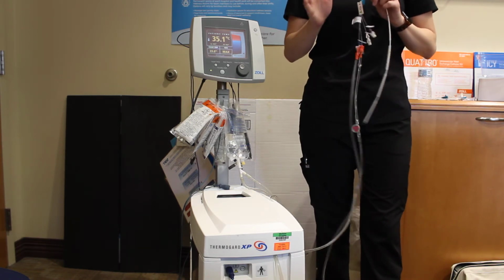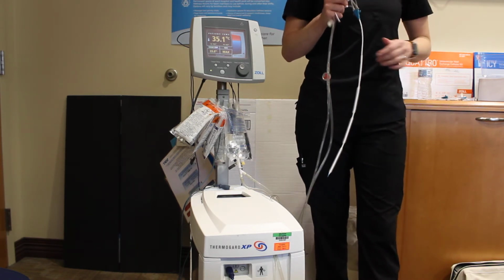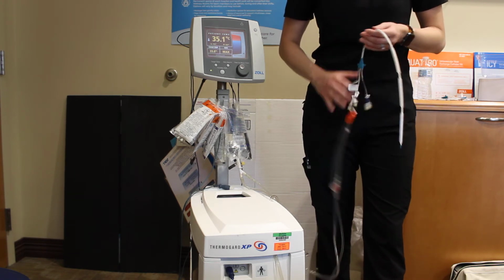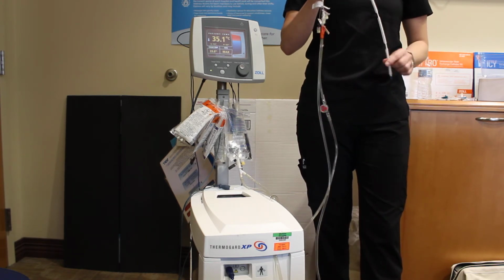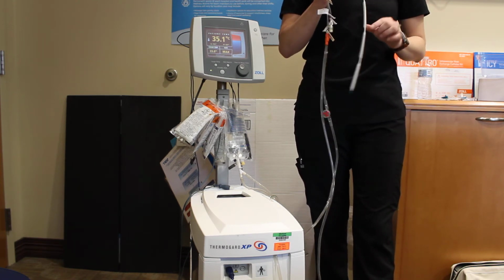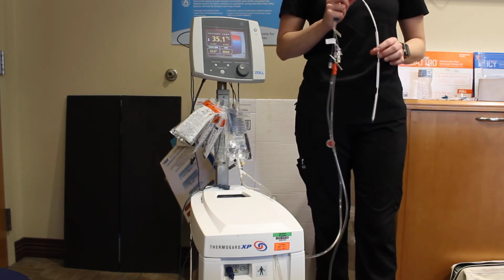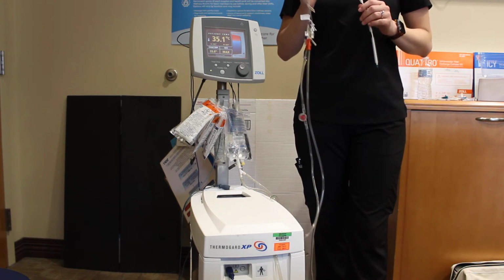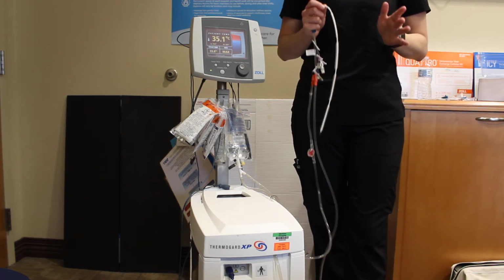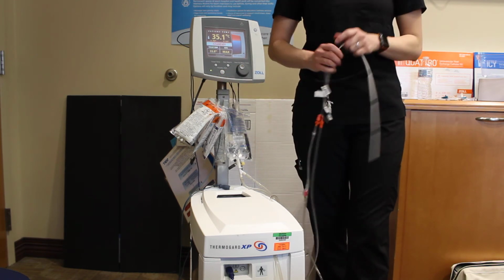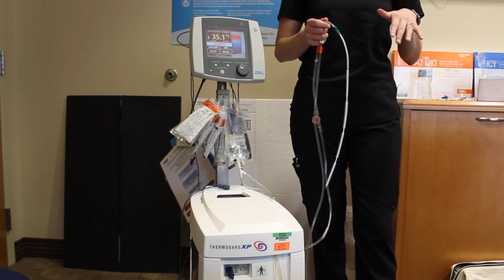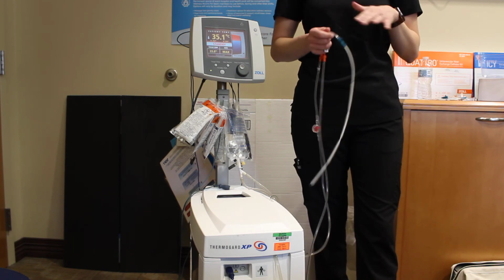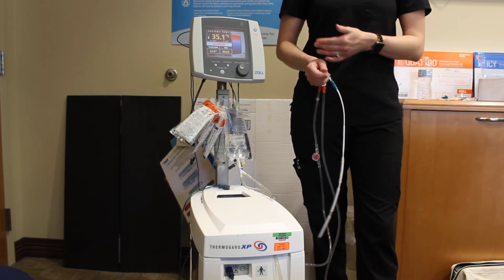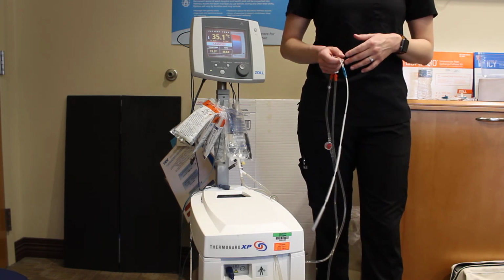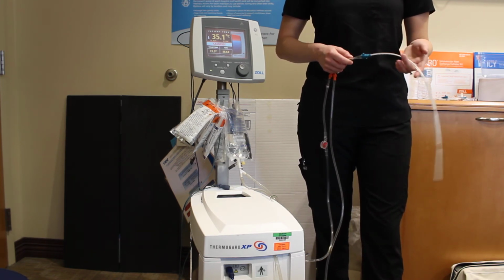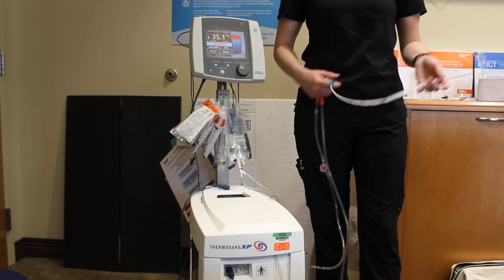However you clean those, these can be cleaned exactly the same. The one medication that you do need to be wary about infusing through this is mannitol. Mannitol will actually crystallize at low temperatures. So if you're giving a push of mannitol, you can pause the machine, give it about a minute or two, flush the lumens really well, push your mannitol, flush it again with several flushes just to be safe that it's out of the line, and then restart the machine. But if you are giving a mannitol infusion, something that's continuous, you'll need to find another IV site for that. Other than that, it's pretty much the same.